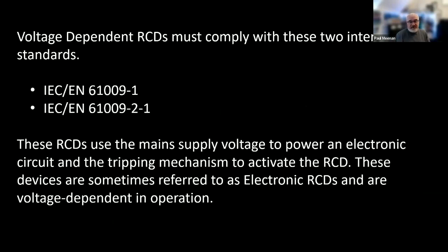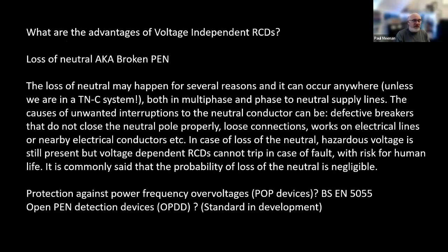Now, the majority of RCDs out there are electronic ones. They're voltage dependent. The older ones, it's always been said, will work if you have a loss of neutral, because if you lose the mains and you still have some energy there and there's a fault, you can still operate that device potentially. What are the advantages of voltage independent? Well, loss of neutral. This is directly from a white paper.